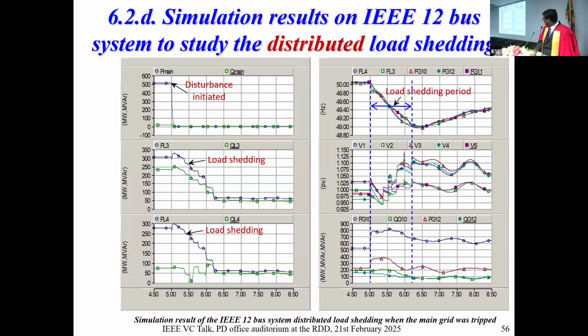So now you can see load shedding happen. Soon after they realize frequency is going down, frequency comes back and automatically restores. These actions are automatic and cannot be done manually; they are fully automated. That means the power system is a very strong, interconnected system where only one frequency is available. Frequency may slowly vary between north and south, but with a rigid system, rarely will both run at different frequencies. When I say frequency varies, it's only by a small fraction. Usually the frequency remains the same.